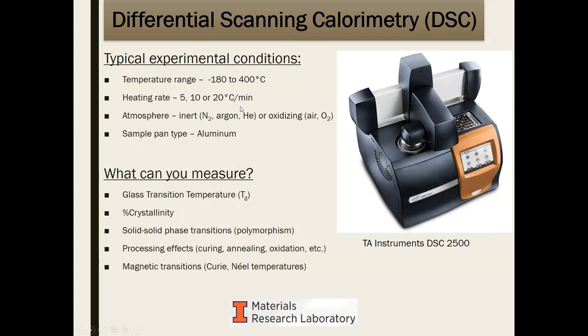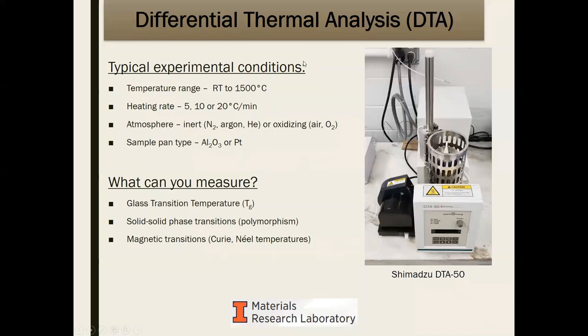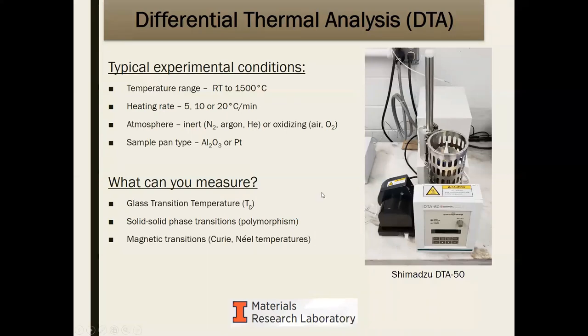Heating rates for DSC are similar to TGA. For our instrument — a TA Instruments DSC 2500 — the temperature range goes from about liquid nitrogen temperatures up to around 400°C. We also have a DTA instrument at MRL, which is that older technique that can go to very high temperatures. It is more difficult to convert the energetic transitions into actual energy units, but you can still identify when transitions occur and at what temperature.